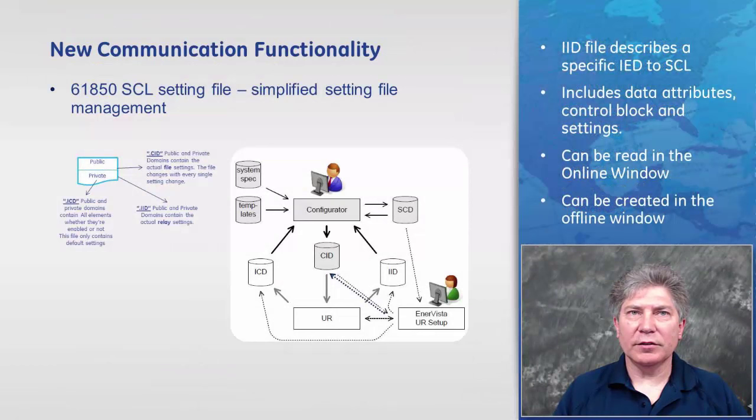The IID file, the instantiated IED description file, describes a specific IED to a system configurator tool, typically more or less configured for its role in a system. The IID file includes the data attributes of the UR device, the control blocks and settings, with all the settings values as they were at the moment that the IID file was generated. A copy of it can be obtained directly from a UR device or from EnerVista UR Setup. The IID files can be read in the online window and created in the offline window.